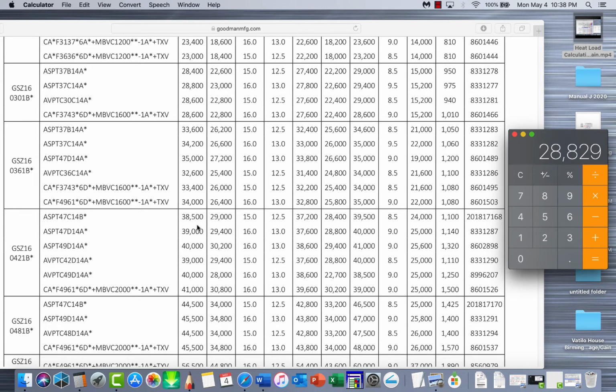Now, total BTUs, that tells you this is the total upper end range of it. This is the lower end range of it. We got to make sure this lower end range is meeting this target number. Minimum. That's the minimum we want to make for that right there. So, based on the house in Texas with the leaky ductwork and everything like that, we see these numbers here in this column are a lot better than this column up here.